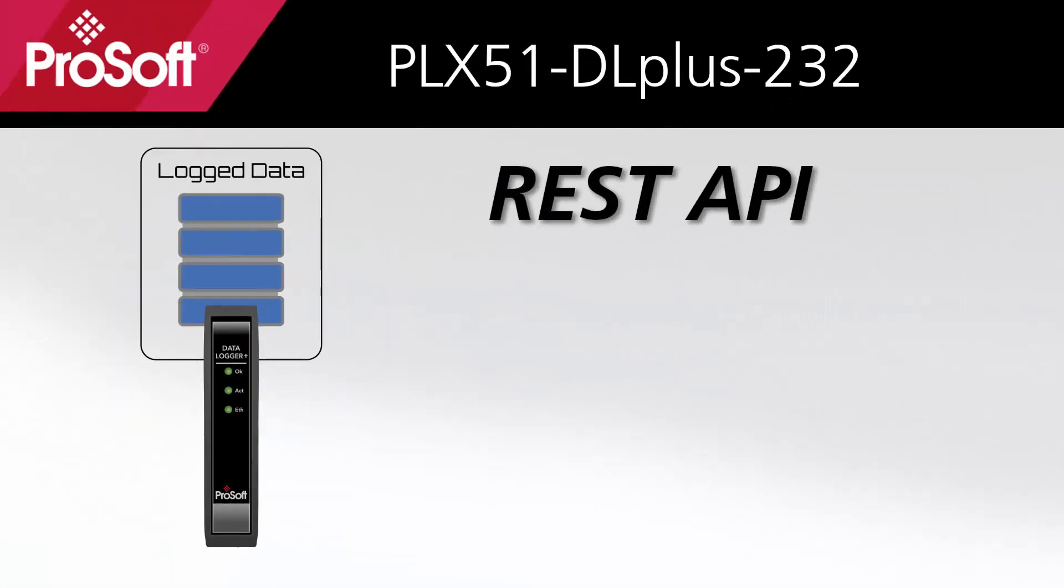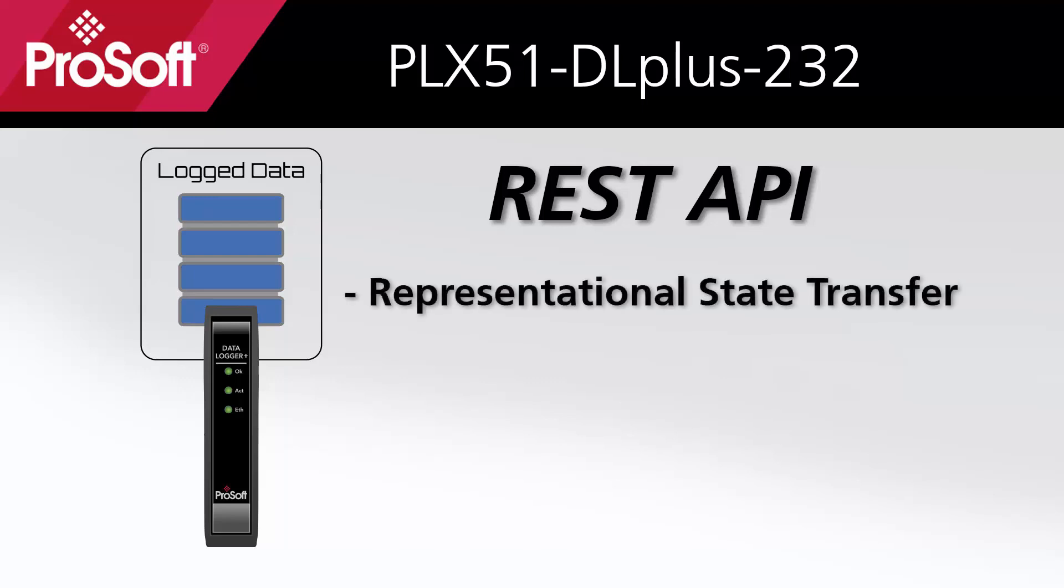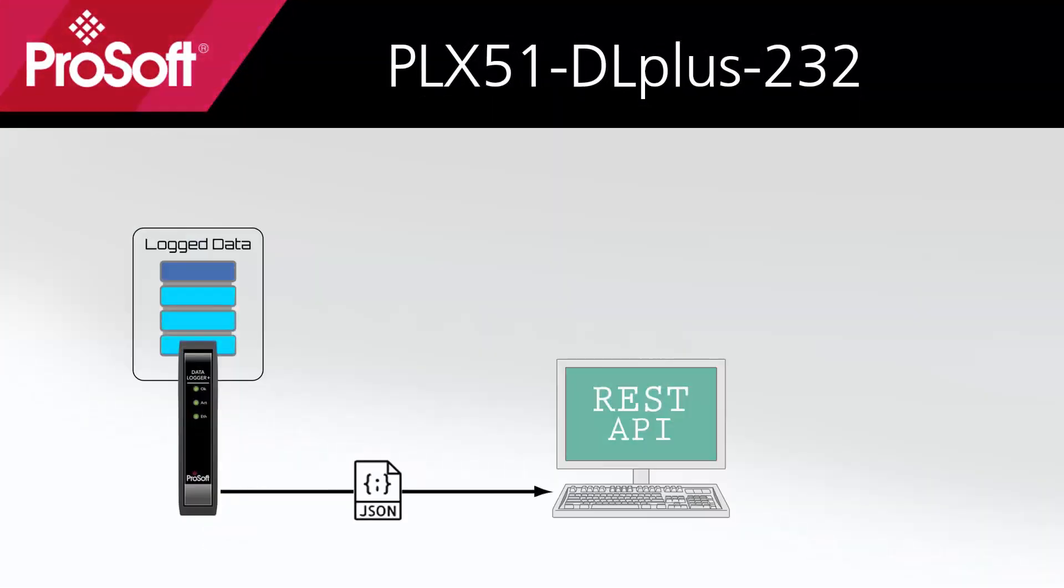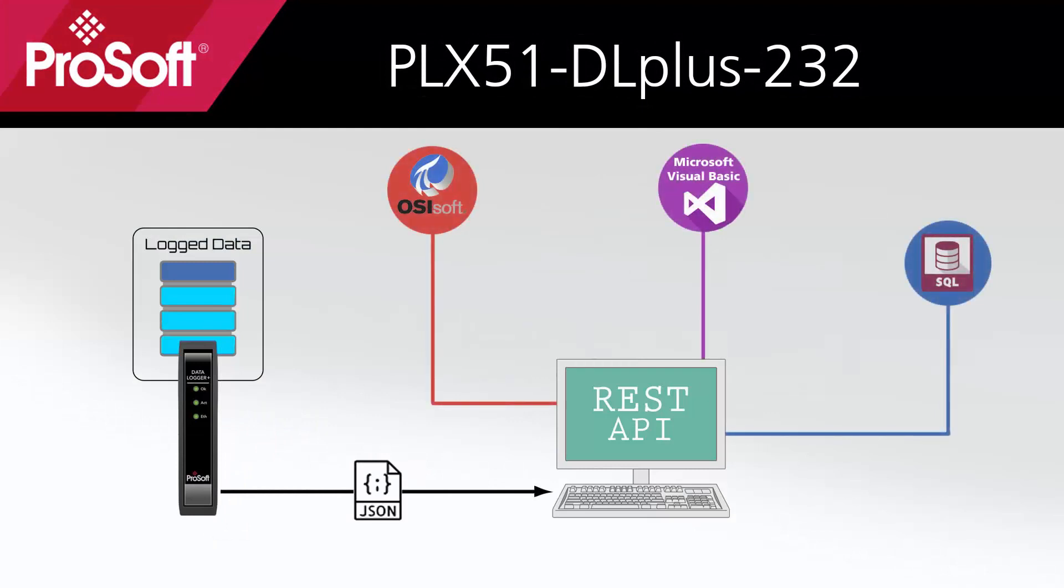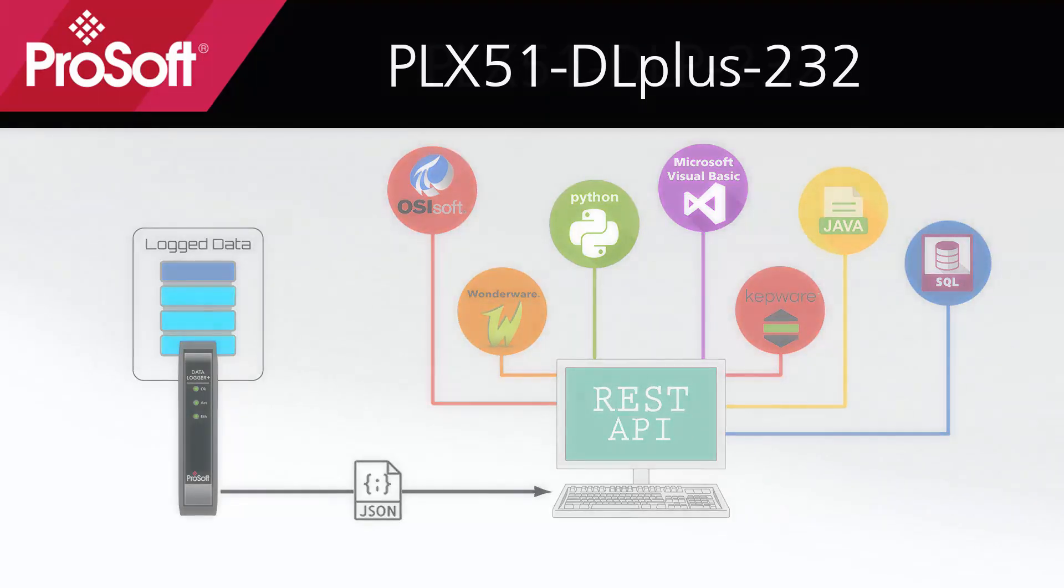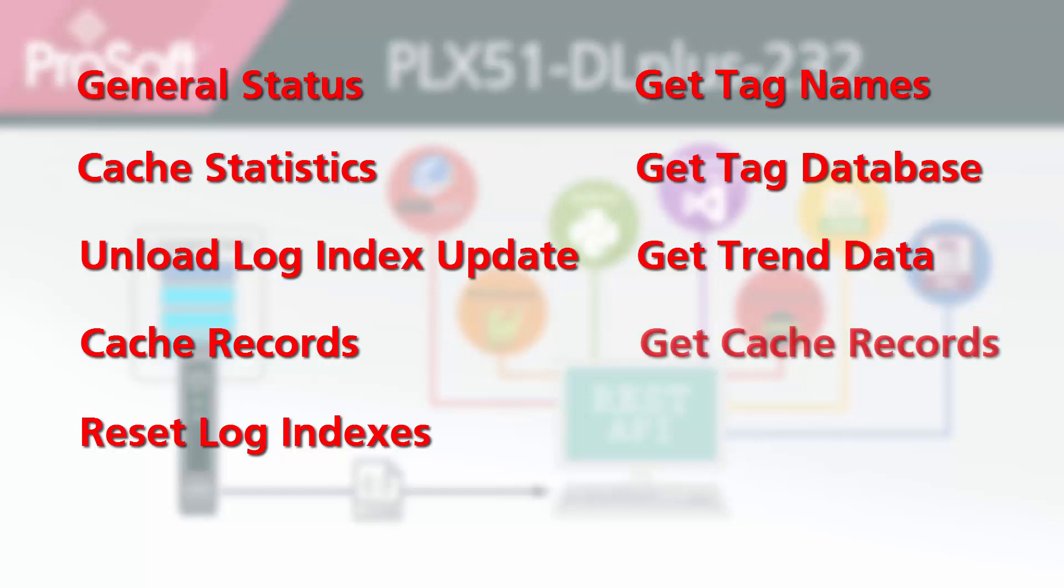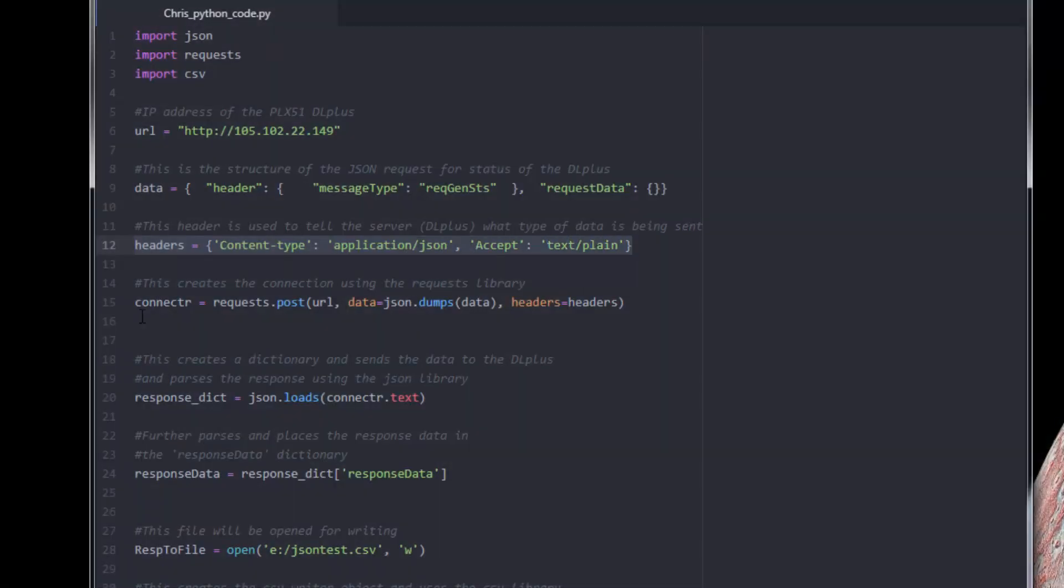Another option we have to access our log data is by using the DataLogger Plus's Representational State Transfer, or REST Application Programming Interface. This is an industry-standard method of calling customizable programming interfaces on a remote server. This gives you unparalleled access and control to the records, tags, and status information within the DataLogger on a nearly unlimited assortment of platforms and programming languages. The DataLogger Plus supports specific APIs for maintaining and accessing data contained within the DataLogger. These include general status, cache statistics, unload log index update, cache records, reset log indexes, get tag names, get tag database, get trend data, and get cache records.